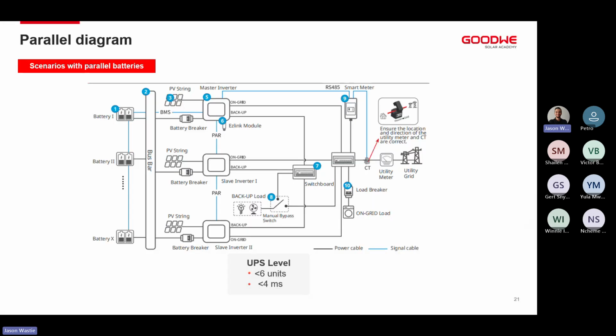Okay, there was one question on how many ES Uniq 6 kilowatt inverters we can parallel. Let me go back to that slide quickly. So when it comes to paralleling our inverters, we can parallel up to 6 units, regardless of the size of the inverter, from 3.6 kilowatts all the way up to 12 kilowatts, with a 4 millisecond changeover time. And the only additional purchase that we need when paralleling the system is the EasyLink module.